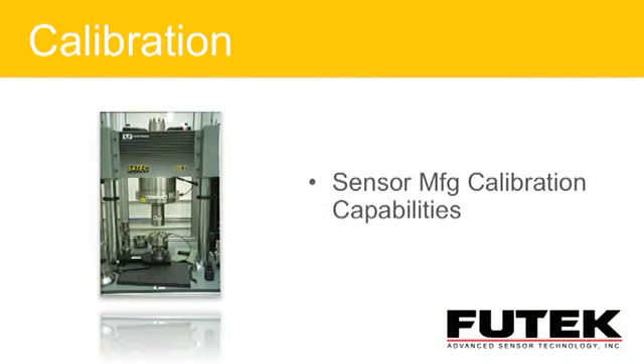On top of all the other considerations, budgetary and whatnot, calibration can also be extremely important. Normally sensors are calibrated under a static or ambient temperature, but maybe your custom requirement needs it utilized in a hot or cold environment, and you want additional data. Some calibration labs can actually perform tests under these conditions, whether hot or cold, and provide the data so you know exactly the characteristics of that sensor in that environment.